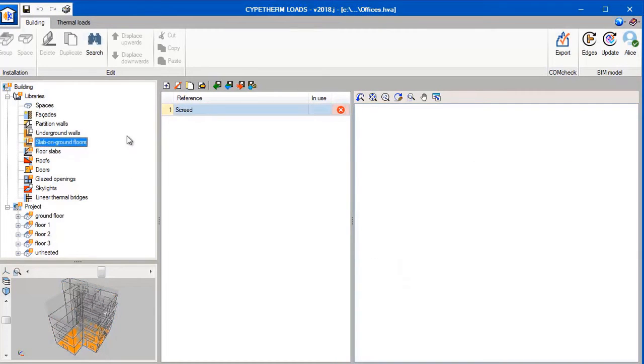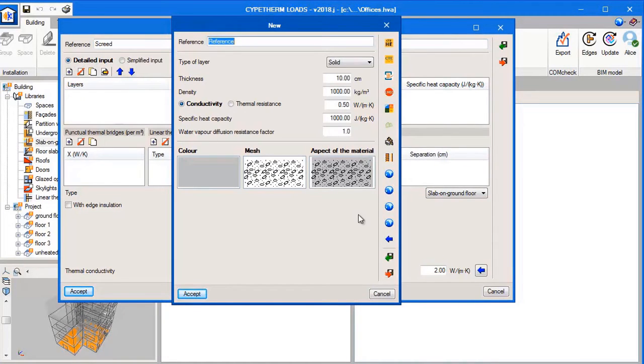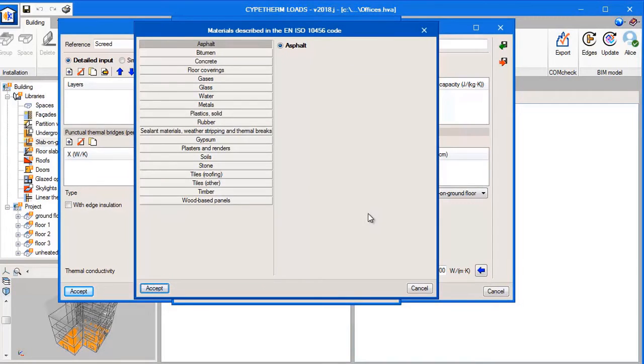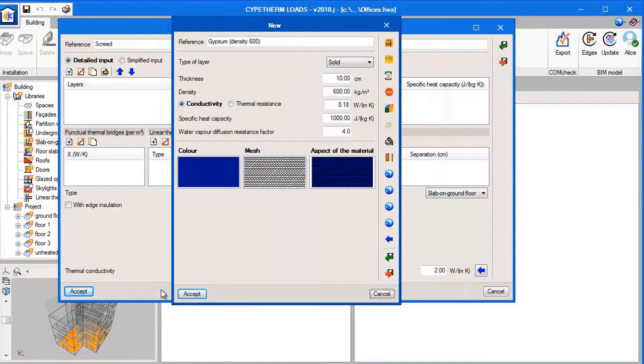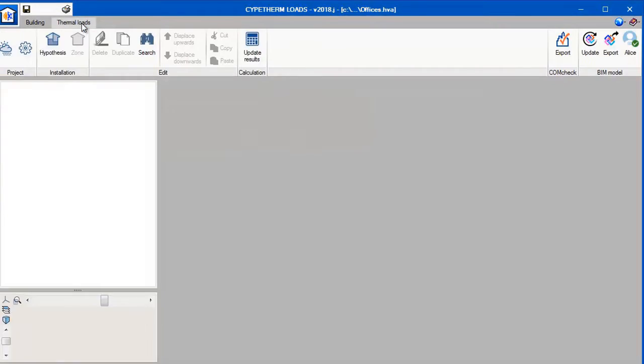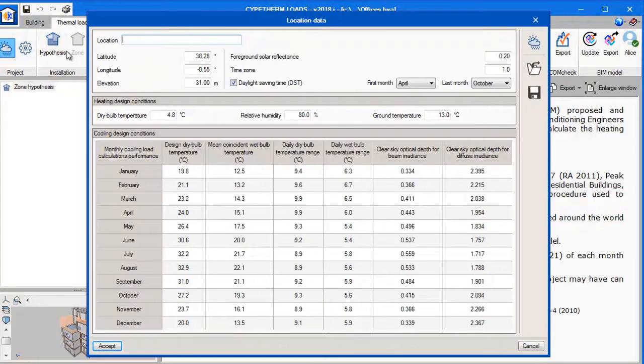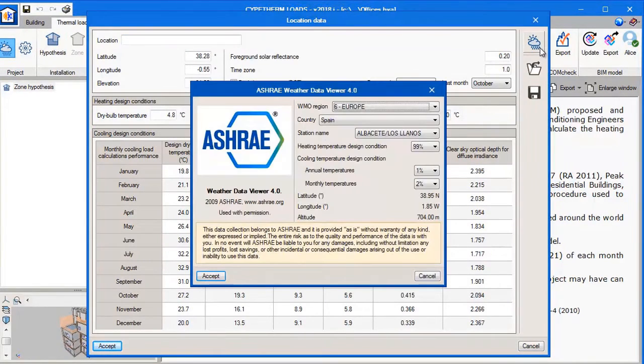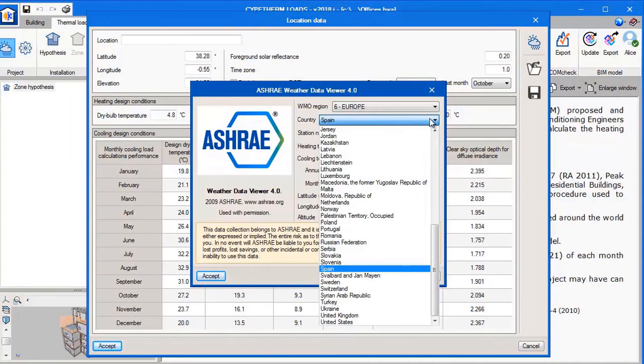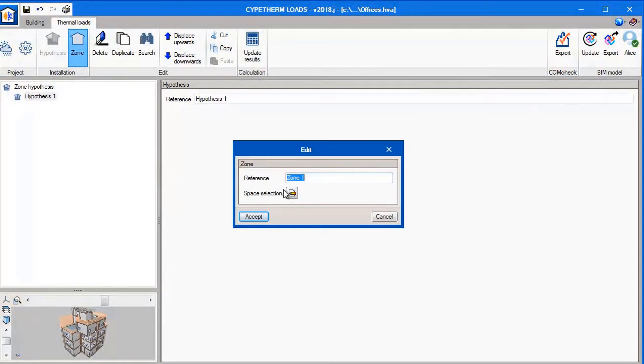We need to create the screed for the building, so we open it up and we can access the library of materials. We can select layer by layer which materials we want to use for the screed of the building. Once we have all the information we need in the building tab, we can move on to the thermal loads tab. We can open up the location data. CYPETHERM Loads has an internal weather database created by ASHRAE, so all we need to do is select the location and the data will be imported. Finally we group spaces into zones and press calculate to obtain the results.